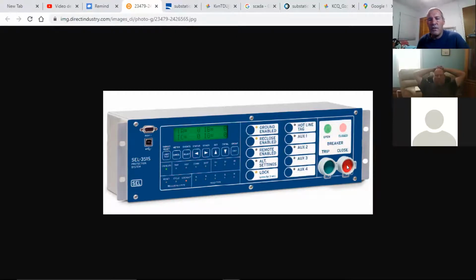Can you understand the safety reasons why? Yeah, because you're not checking if there's any kind of fault, you're just closing it. Right, you don't know what kind of faults you have on the line. You're really not 100% sure if anybody is working on the line. You don't know if that line has been reported somewhere else as down on the ground. The only capability you have right now is open, and that's for safety reasons.